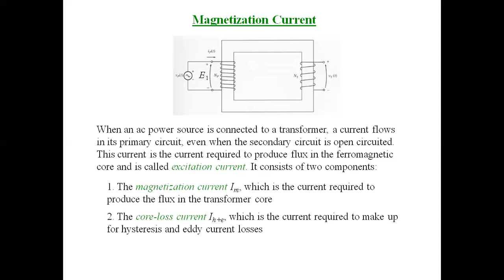This current is the current required to produce the flux in the ferromagnetic core and is called excitation current. It consists of two components: one is magnetization current, another one is core loss current. That is, two components, core loss component and magnetization component. So the no load current is divided into two components, magnetizing component and core loss component.